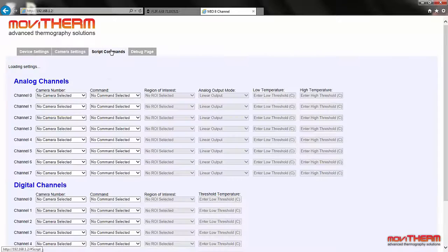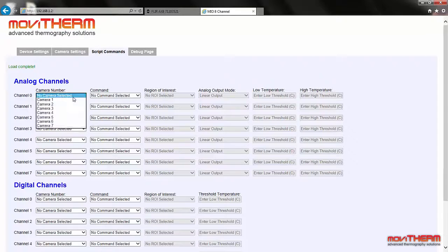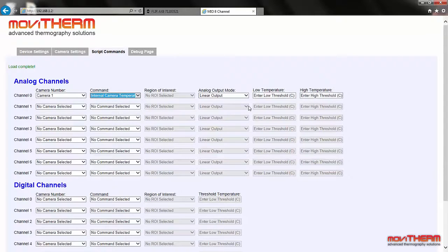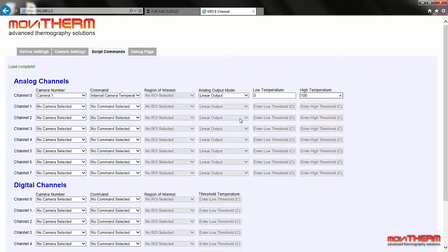Now we're ready to set up the alarm. The script commands page is used to configure the Mio I/O functions. The eight analog and eight digital output channels are arranged vertically from top to bottom on the left side of the screen. We will set the analog channels first. To set up analog channel 0, we select camera 1 from the camera menu. We need to set up a command — we want to track the internal camera temperature in the upper LED display on the Mio system panel, so let's select internal camera temperature from the pull-down menu. Since this is an analog display, we need to define the 4 to 20 milliamp mapping. We will set the analog output mode to linear output and enter the low and high temperature limits for the 4 to 20 milliamp scaling — setting the lower limit to 0 and the high limit to 100 degrees Celsius.